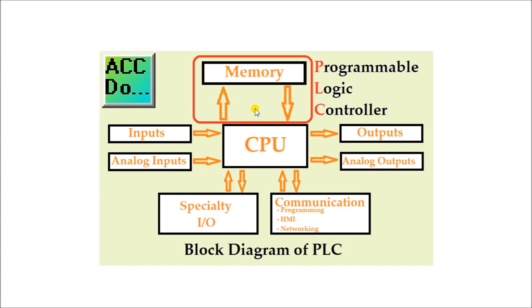Volatile memory in the PLC means that when power is removed from the unit, the information is erased. Non-volatile memory does not lose its content when the power is removed. Random access memory or RAM is a form of volatile memory. Since RAM memory is the quickest, your PLC program will run on RAM volatile memory. PLC platforms assign some parts of RAM to be retentive or other parts non-retentive. Refer to the specific manual on the PLC controller that you are programming.